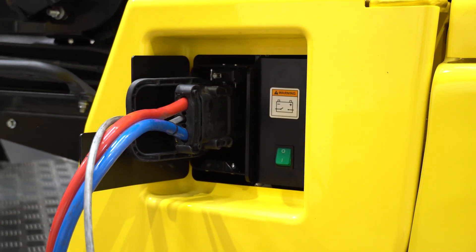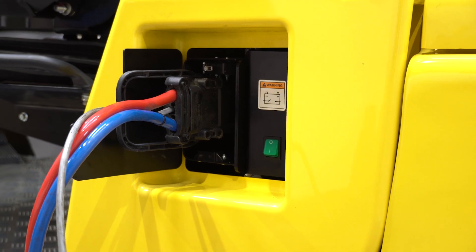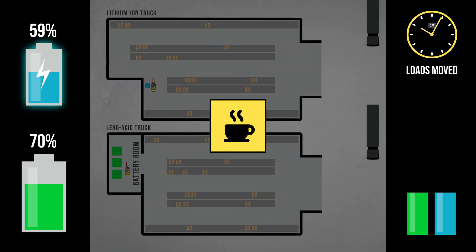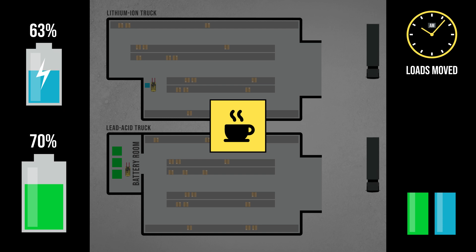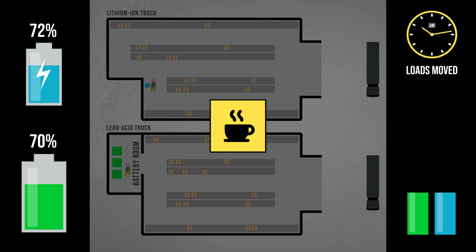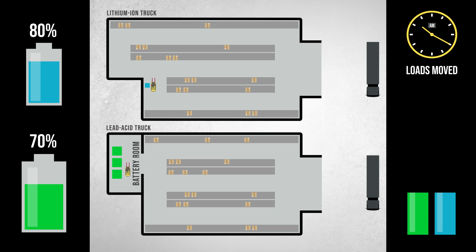With lithium-ion battery technology, there is no adverse effect on battery life by using opportunity charging. The days of needing a lengthy full charge are in the past. The 20-minute top-up charge during the coffee break has topped the lithium battery up to 80% for the next portion of the shift.